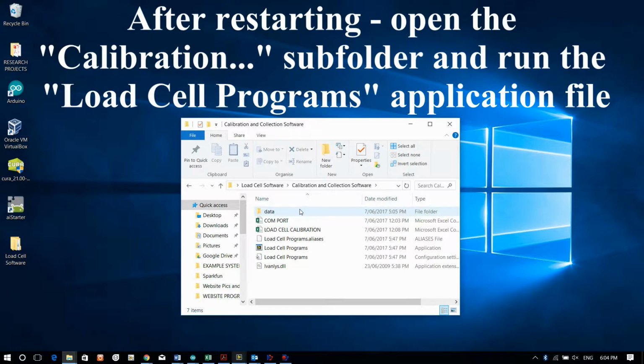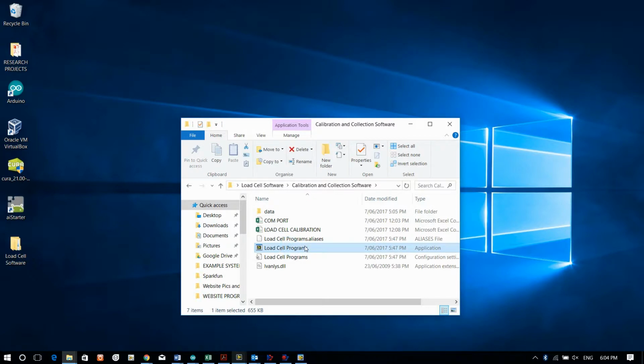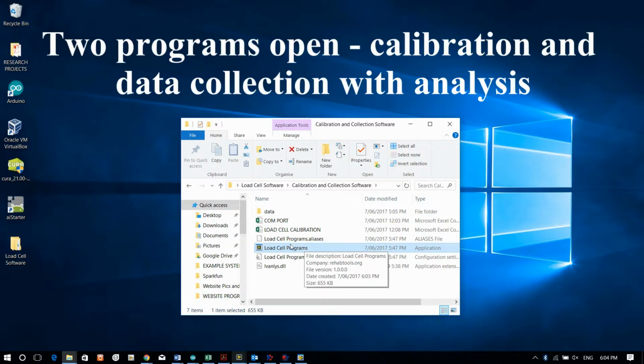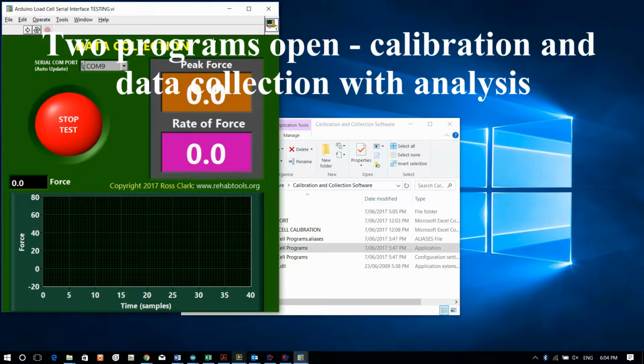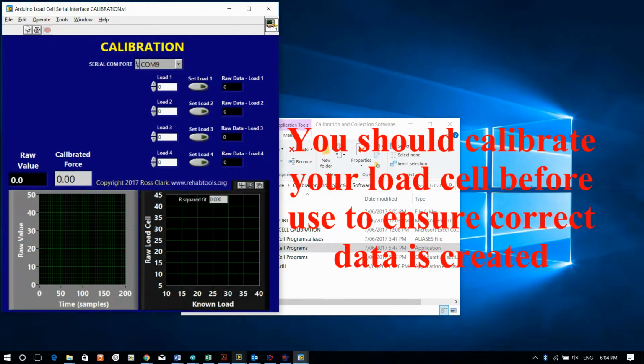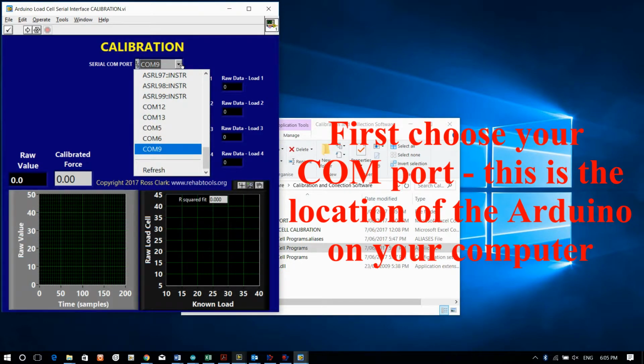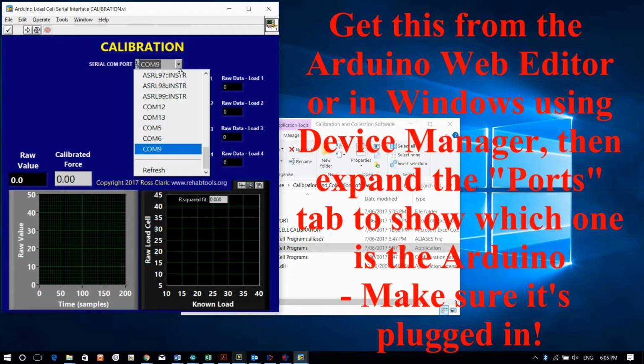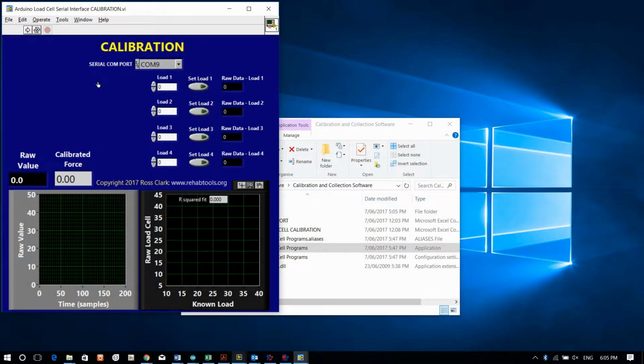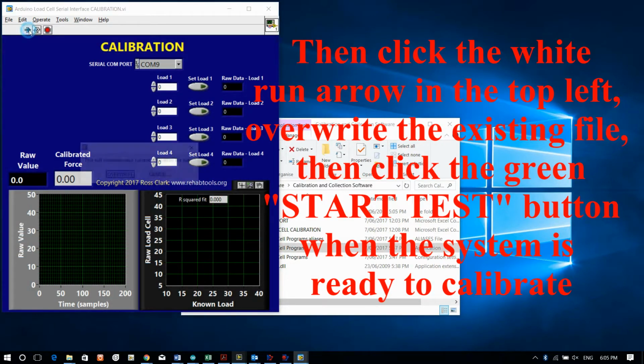So the computer's restarted, I'm back to the folder, click Calibration Collection Software, and click that Load Cell program. It opens up two programs. One is a calibration, so we'll leave that one first. We're actually going to calibrate it, so it's really easy. What you need to do is have the Arduino plugged in with the load cell, and then you choose your COM port. Mine's COM port 9, so you can click that drop down arrow and click that refresh button if you need to. Now we click the white arrow and click overwrite.